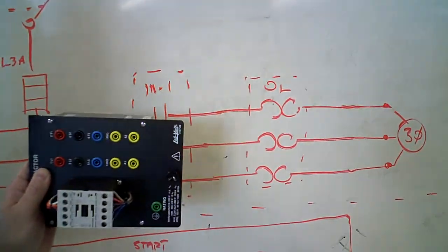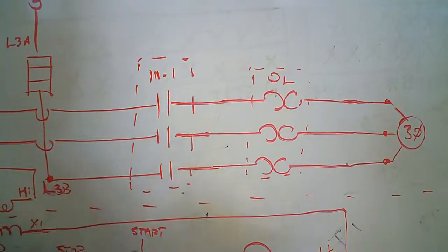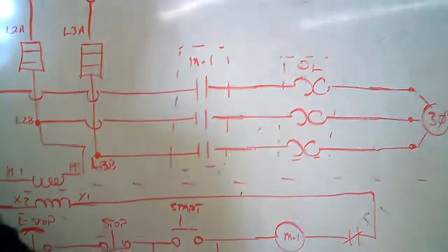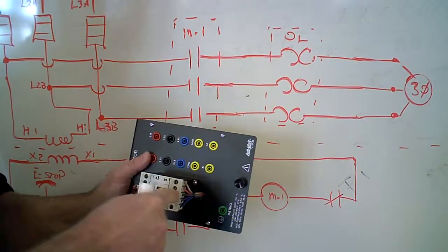And then we already talked about the contactor. The contactor here, that was up here. This is labeled M1. Well, everything in a schematic that's labeled M1 goes on that physical device. So it means it's mounted physically in that arena. So M1 here, M1 here, M1 here. These three contacts are inside of this one, two, three.